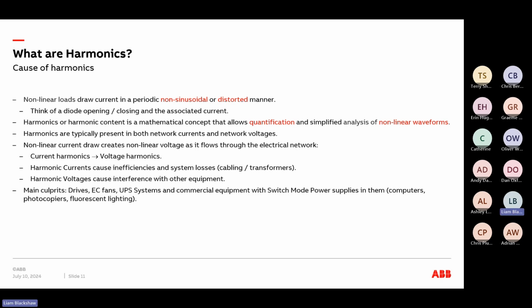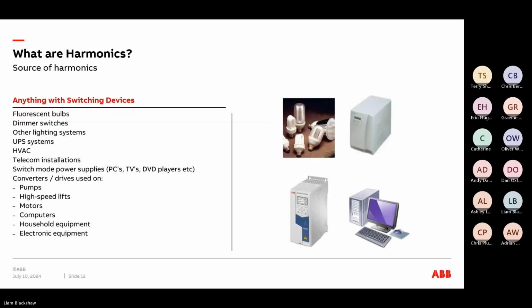They're the key culprits, and I'm probably going to sound biased because of my background, but whenever we fit or install a variable speed drive onto a system, it's always the drive that's blamed. It could be to a certain extent, but in some cases it's the straw that broke the camel's back. It could be that little bit that we add to it that sends it over the thresholds and causes issues on the supply system. So it can be to blame, but it may not always be the culprit. And it's always about understanding what you've currently got on your distribution system. So yeah, source of harmonics, we've pretty much touched upon that. There are a few more examples there, but it's basically anything that has some form of switching device in it.